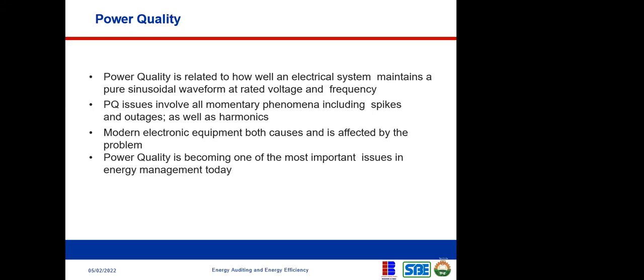Power quality issues involve all momentary phenomena, including spikes in voltage and outages, as well as harmonics — we're going to talk about harmonics as well. Modern electronic equipment both causes and is affected by the problem of power quality. So power quality is becoming one of the most important issues in energy management today, because if your power quality is bad, it's going to affect a lot of things. It can blow out your machines, it can affect your equipment, and it can also lead to death. So it's important that we, as energy auditors, though not mandatory, still pay attention to the power quality of the facility that we are auditing.